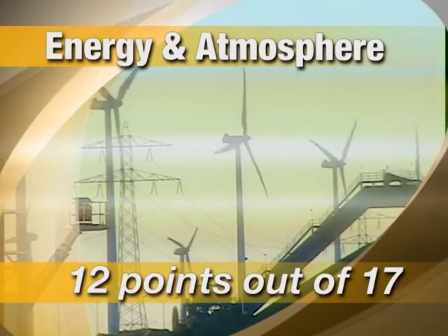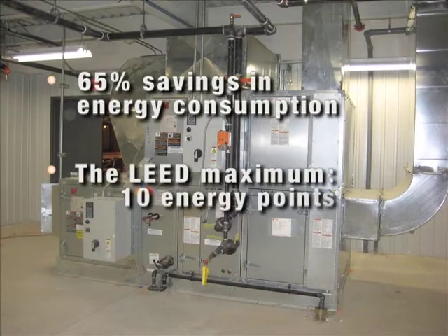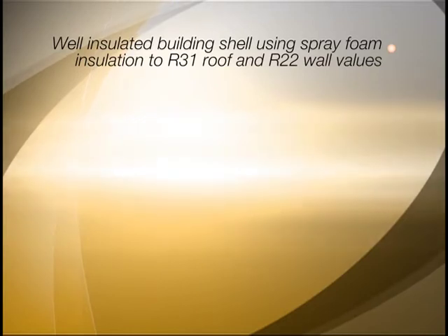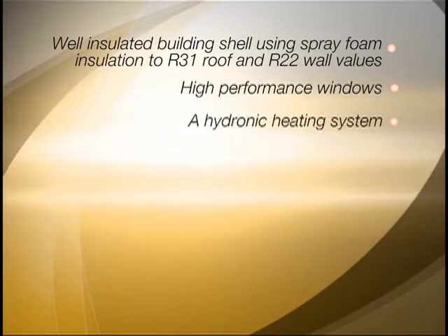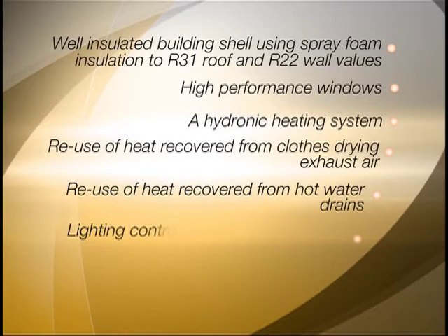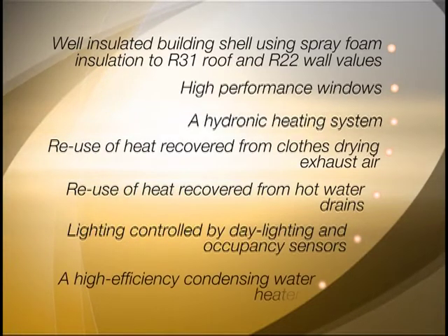In energy and atmosphere, energy modeling shows that the building will achieve 65% savings in energy consumption, giving it the maximum 10 energy points, as a result of several excellent building design features: a well-insulated building shell using spray foam insulation to R31 roof and R22 wall values; high-performance windows; a hydronic heating system; reuse of heat recovered from clothes drying exhaust air; reuse of heat recovered from hot water drains; lighting controlled by daylighting and occupancy sensors; and a high-efficiency condensing water heater.